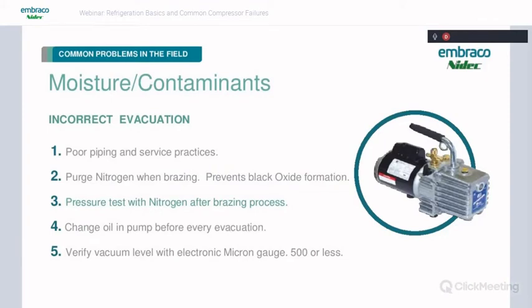So moisture and contaminants can be introduced into the system through poor piping and service practices. We want to make sure we're purging nitrogen when we're brazing at about 2 psi. This prevents the black oxide formation on the inside of the tubes. In the old days in air conditioning, when you were using mineral oil, it was very forgiving. That oxide may stay put. But with the new systems, POE oil is like a solvent. It's going to scrub these contaminants off the inside of the tube, and it's going to clog things up.